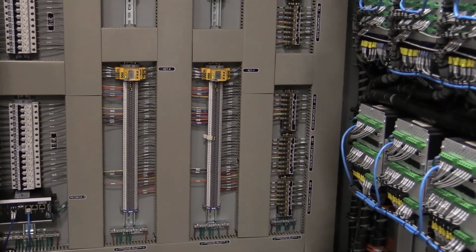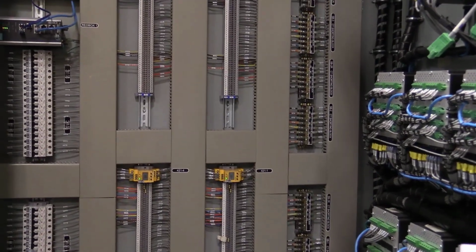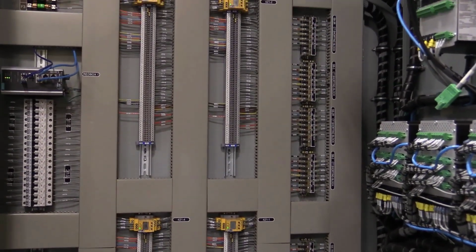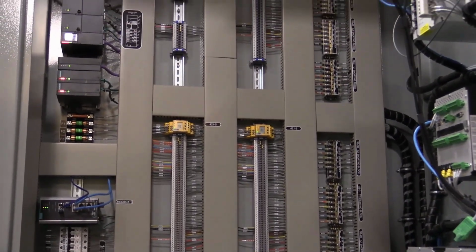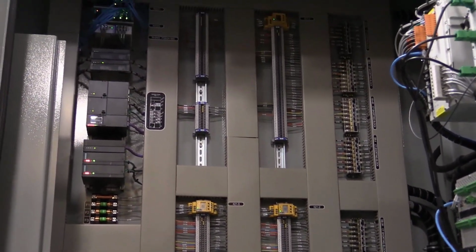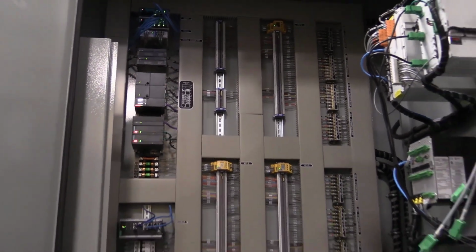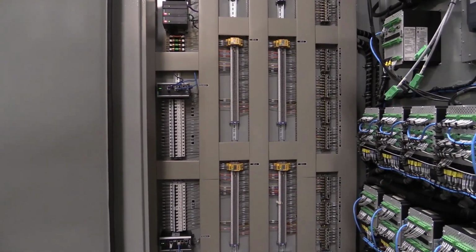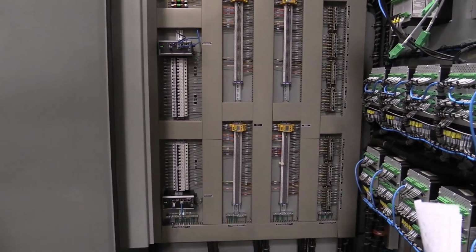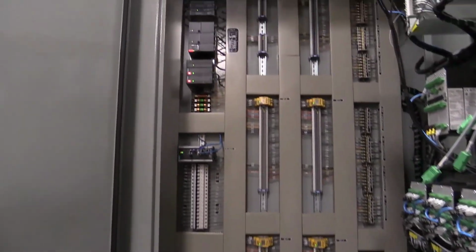A key thing to point out here is that from the customer's point of view, they are bringing in phase A, B, and C voltage signals for the power quality and for the relaying package. They bring in a ground conductor and 3 medium voltage power cables. All other communication is through 61850 protocol, or through Siemens using Profibus or Modbus.